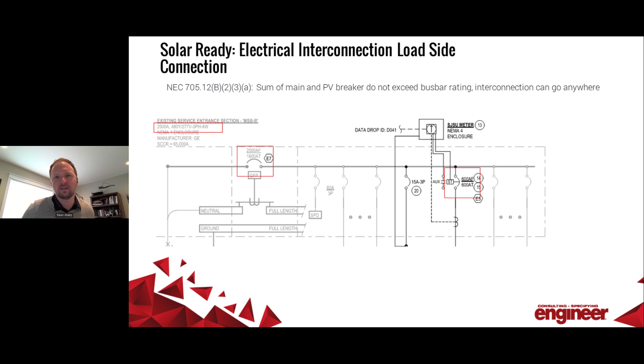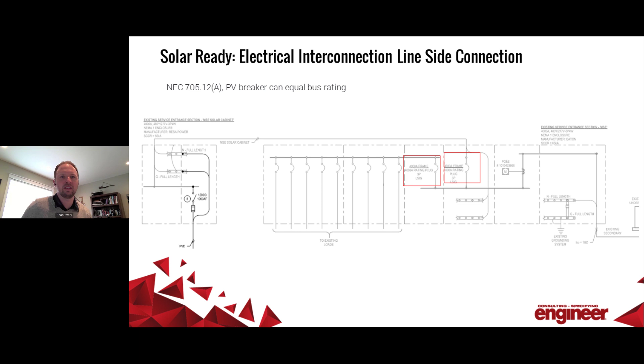For larger systems with a line side connection, the PV system size could basically be up to the rating of the bus. Some clients now are going solar ready in this fashion, adding a solar connection cabinet, for example on here, so that when they install solar, they don't have to shut down their main building service. This allows some other complications, though, such as what happens if your system is significantly smaller than, in this example, 4,000 amps. You're going to have to somehow size everything down in the future.